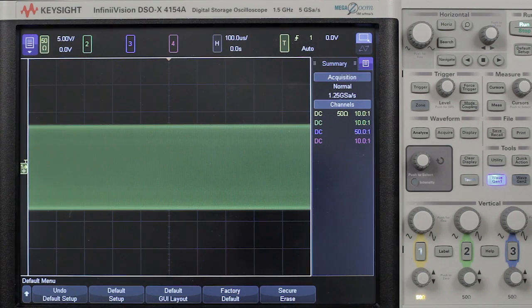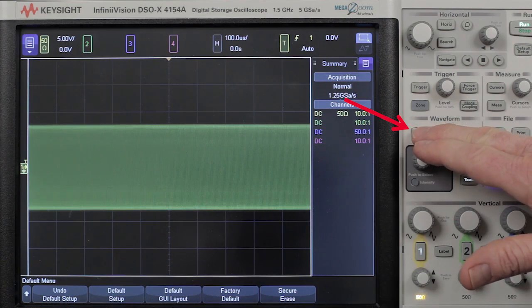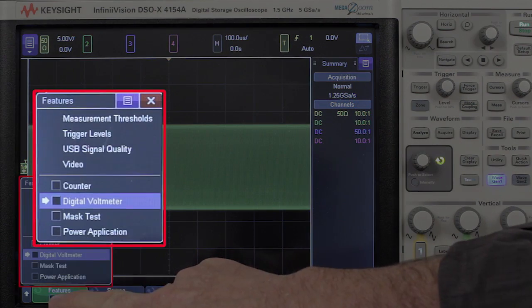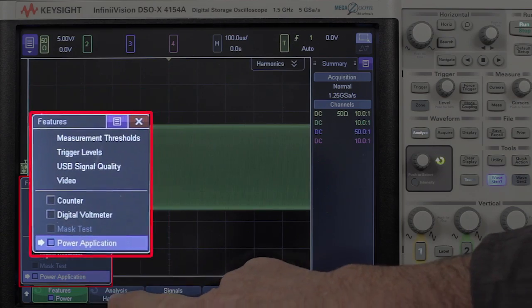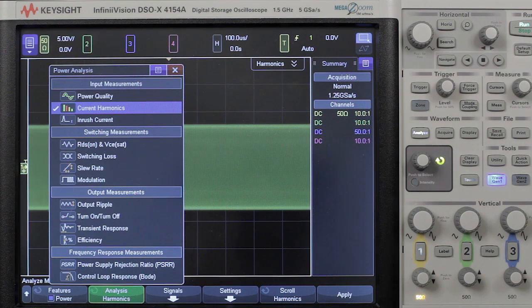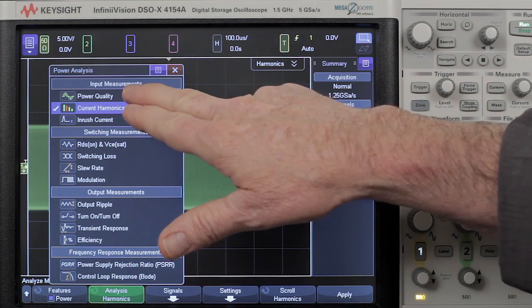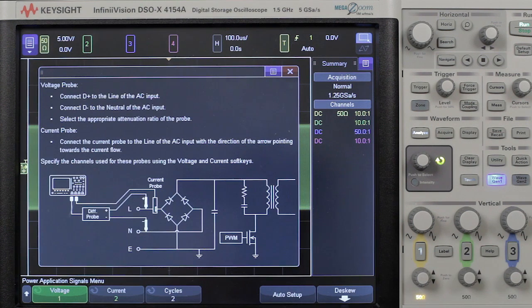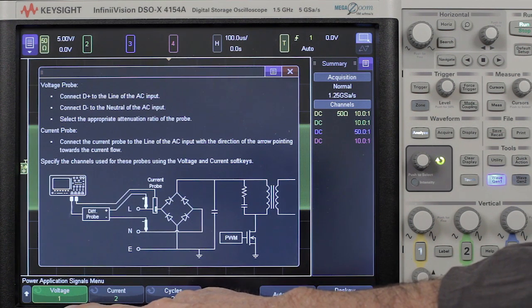We're going to begin with a power quality measurement on the PTU, or the transmitting coils. Begin by connecting your current probe to the PTU coils, as well as the differential voltage probe across them. Let's begin. I'll select the Analyze menu, and then go into the Power Application. These are all the automatic power type measurements we can perform. This was optimized for switch mode power supplies, but there are a few of them we can use on magnetic charging. We're going to select Power Quality, go into the Signals menu. Here we can assign which channel is the voltage.